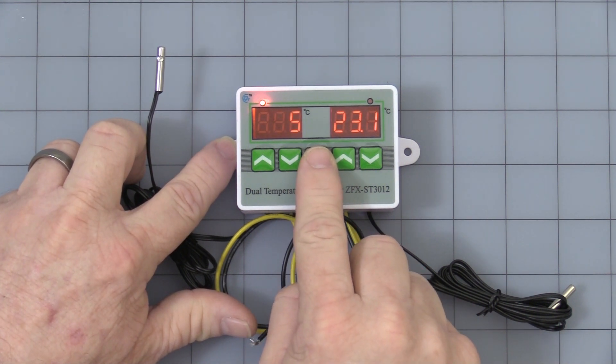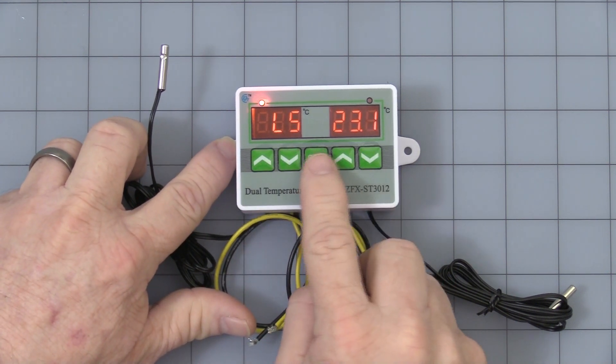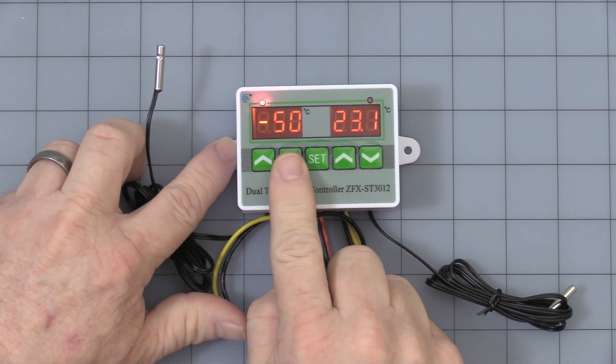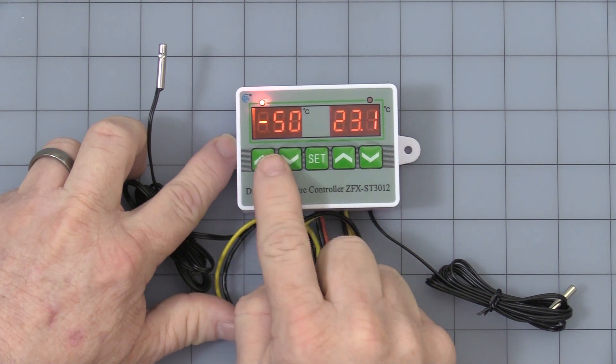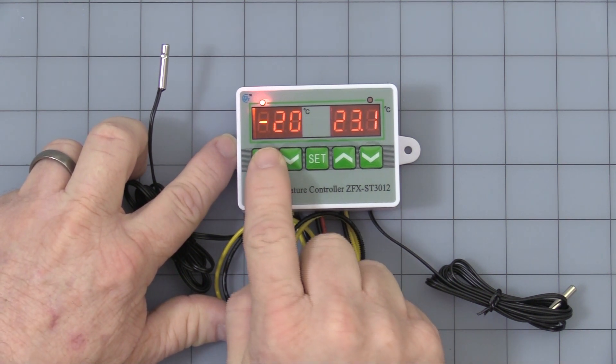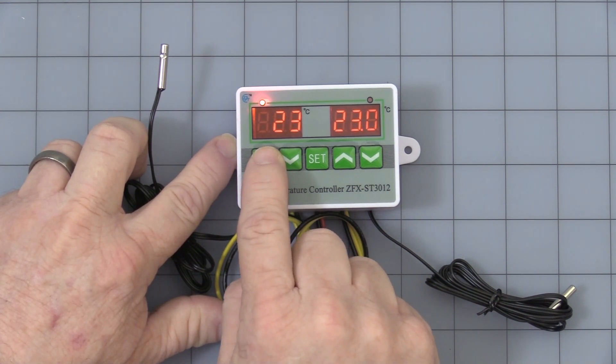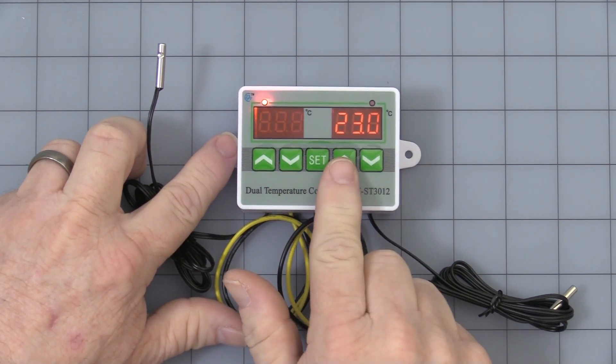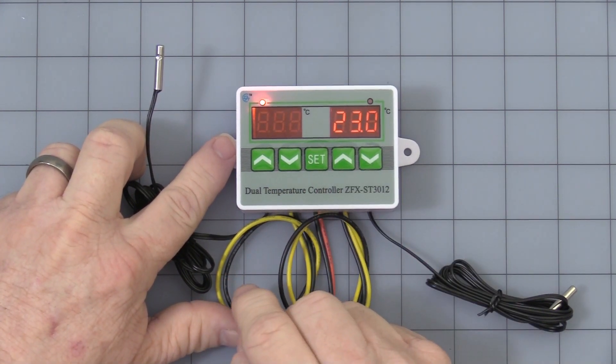Next setting is LS. Now LS, if I hit the set button, that is a low temperature alarm. It comes factory set at minus 50 degrees Celsius. Still in minus. Now if we run it up to say 23 degrees, there again, you leave that alone for a few seconds. When it stops flashing, it's back in the operation mode.